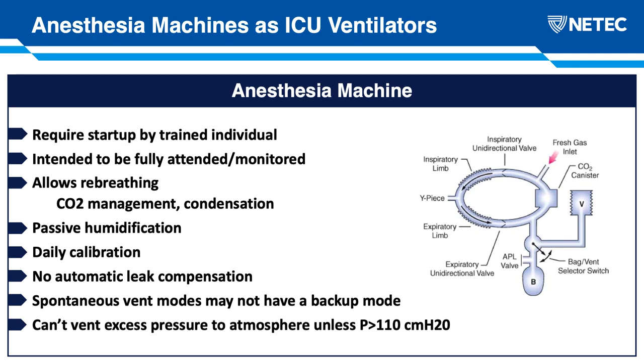But the other implication of rebreathing is that there's an increased buildup of condensation in both the breathing circuit, the portion that we can see, and the portion inside the machine. And we know that prolonged exposure to high levels of moisture on the inside of the machine can lead to breakdown of some of those inspiratory and expiratory valves. So this is something that we have to mitigate, and we'll talk about that in just a few minutes. And because of that consideration, we typically prefer the use of heat and moisture exchangers rather than active humidification. So it's really more of a passive humidification process.